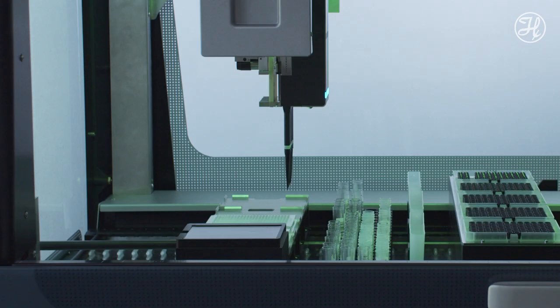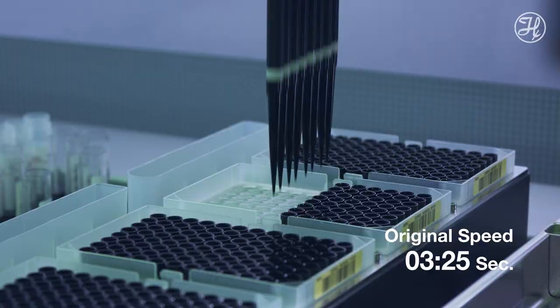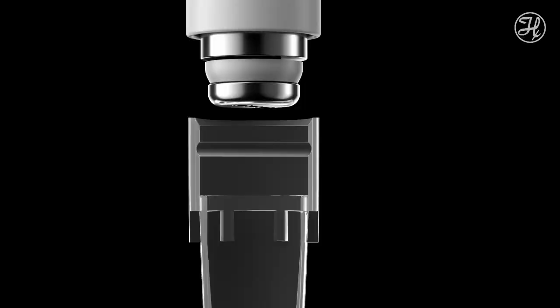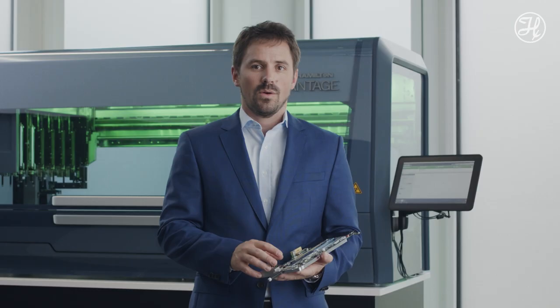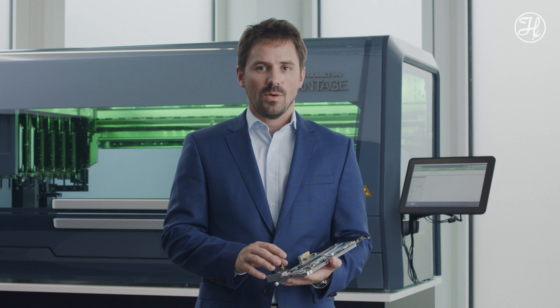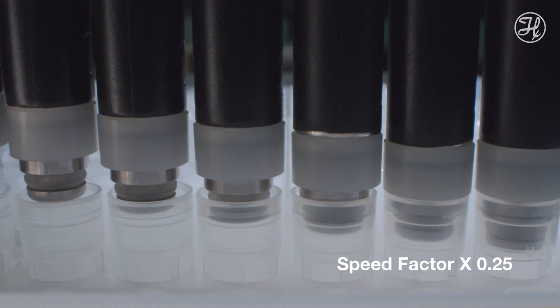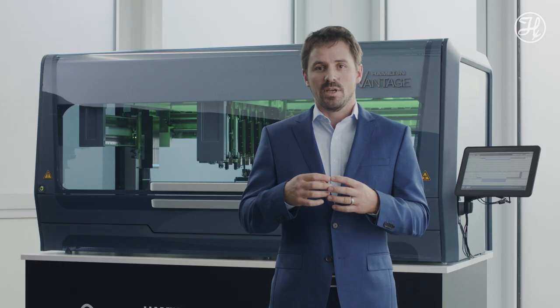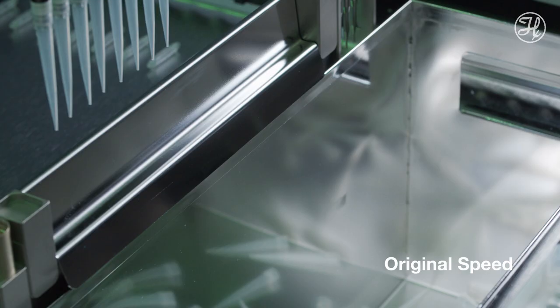We have also completely reinvented the way tips are attached. The full tip pickup cycle now takes less than 4 seconds. The rotary motor for tip coupling has been replaced by a solenoid and a ball lock mechanism. Using this technology we are able to couple a tip literally within milliseconds while tightness is assured by a dedicated seal at the end of the channel. This saves an average user hours and hours of time which can now be spent pipetting rather than picking up and ejecting tips.